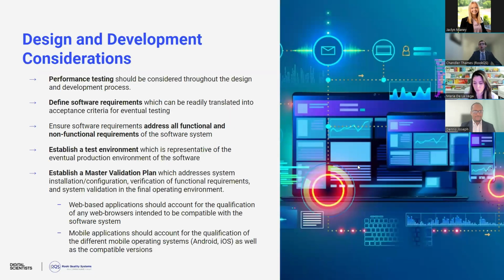So we'll get into some more detail on performance testing requirements and design and development considerations. So again, performance testing is something that should be considered throughout the design and development process. You don't want to completely finalize your design and your device before you start thinking about performance testing. In some instances, performance testing might be difficult to perform based off certain design considerations. So I want to make sure that's something that's at the forefront as you're starting to define some of your design requirements. So the software requirements on that note need to be readily translated into acceptance criteria for eventual testing.